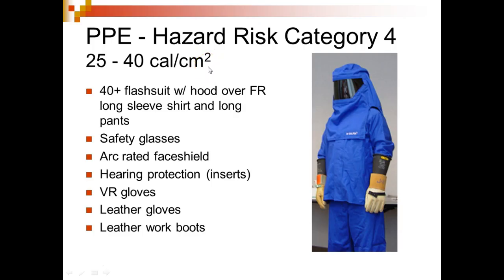And this is 25 to 40 calories: 40+ flash suit rated with hood over fire rated long sleeve shirt and long pants, safety glasses, arc rated face shield, hearing protection inserts. They don't want you to wear what we call Mickey Mouse ears, they want the actual insert ones. Voltage rated gloves for what you're going to work in, plus leather gloves on top of that and leather boots.